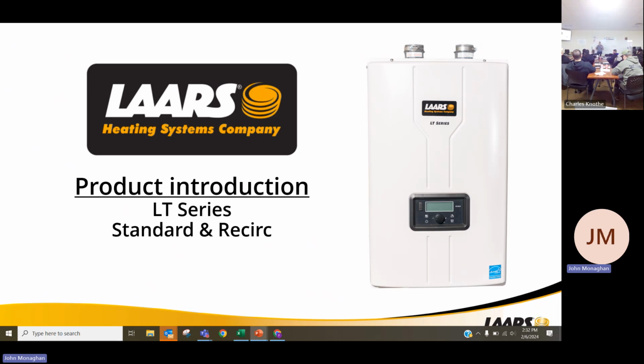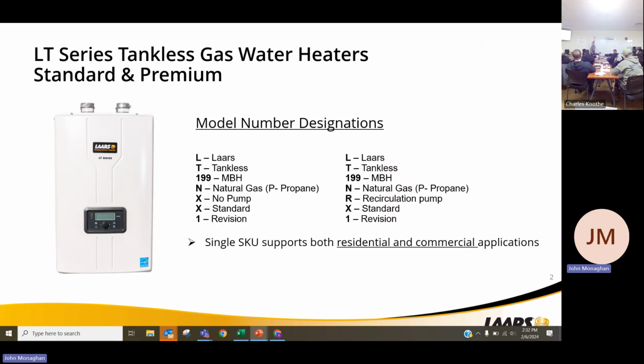It's not a sealed heat exchanger like some of the other products on the market. Designating 2 products, X is going to be no pump, R is going to be pump. The standard model can also be your commercial model. Flip of a switch and the changing of a setting, that thing can go to 180 degrees, and we can cascade them and common vent them. We have rack systems with venting and piping for them, so they can fit some of your commercial applications.